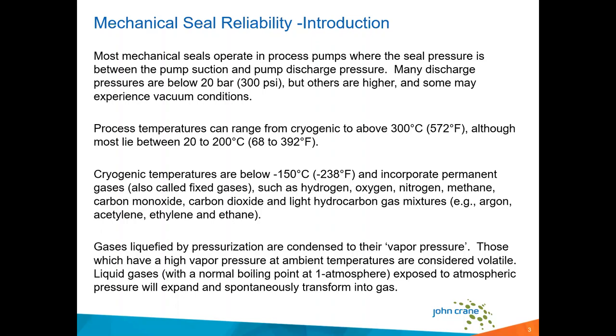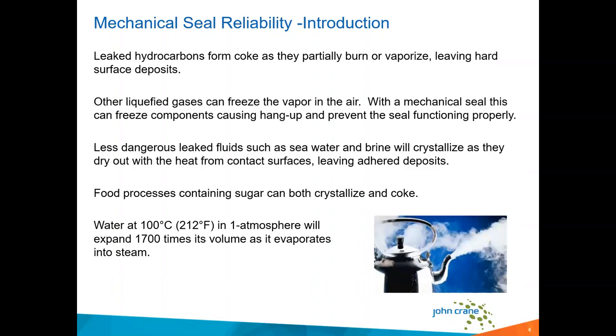Obviously, if the fluid is going to change state, when we talk about ethylene, for example, any kind of rapid drop in pressure is going to result in some fairly significant temperature changes. Being mindful of that gives us a better understanding of how we need to approach the application and also troubleshoot it on the back end. So changing state of the fluid is a big concern. It's a concern in ethylene services and in many hydrocarbon services in refineries as well. But even in some other streams, the actual changing state of that fluid is something we concern ourselves with as seal suppliers, certainly in the application stage.